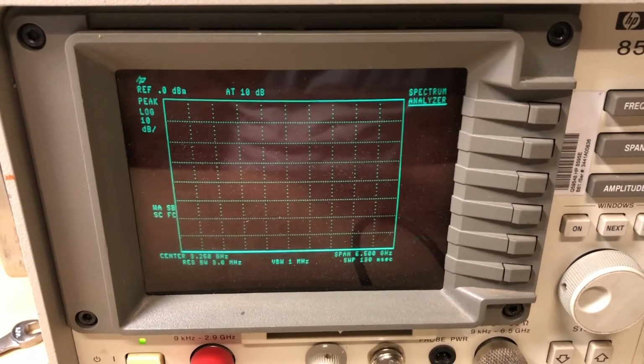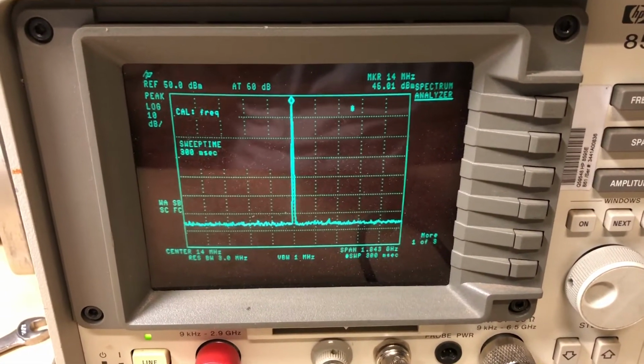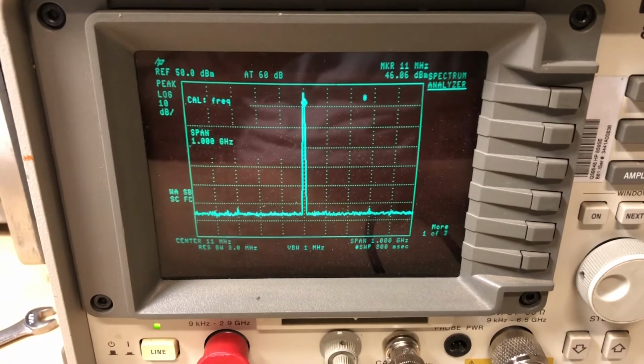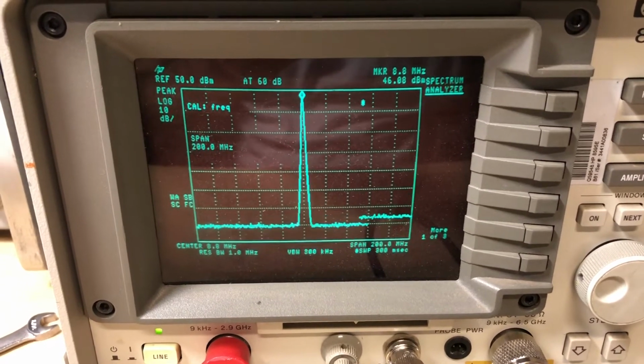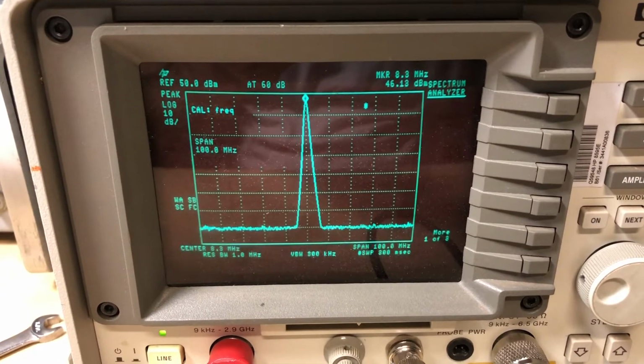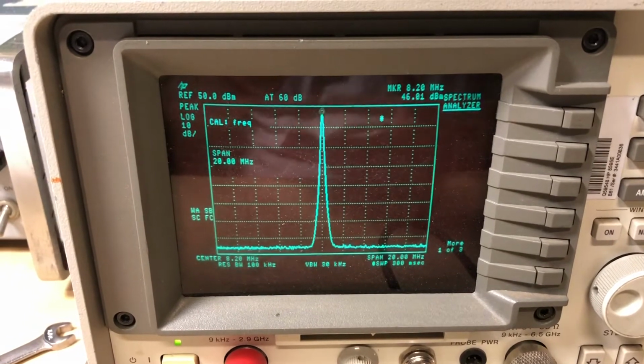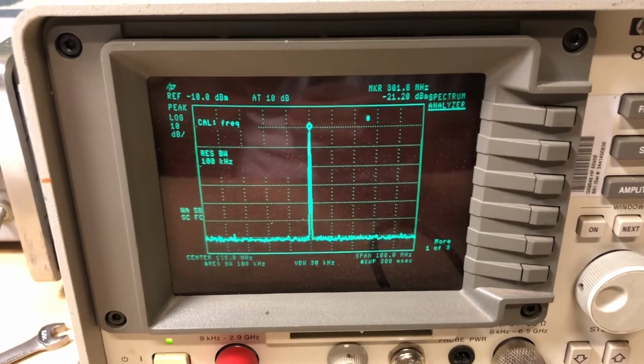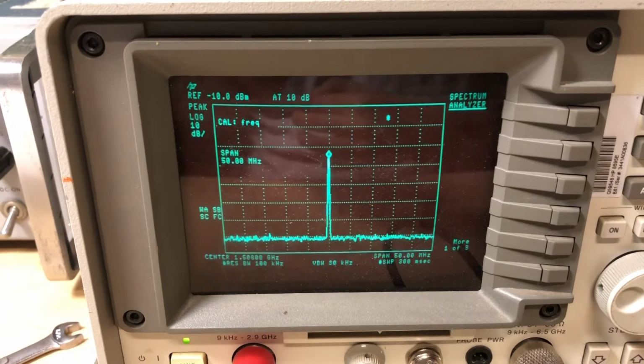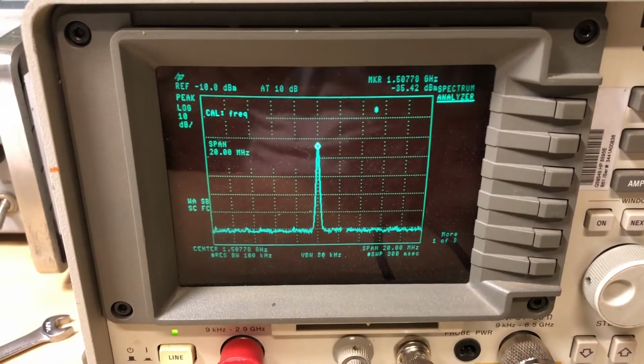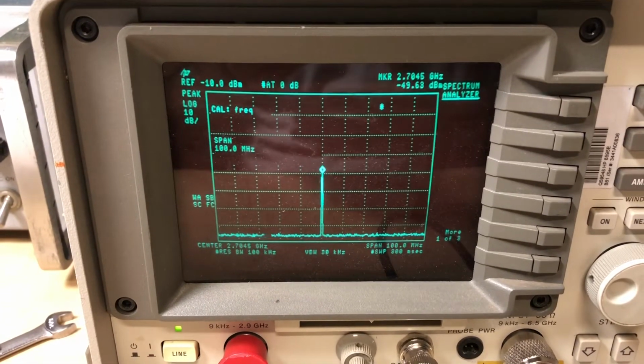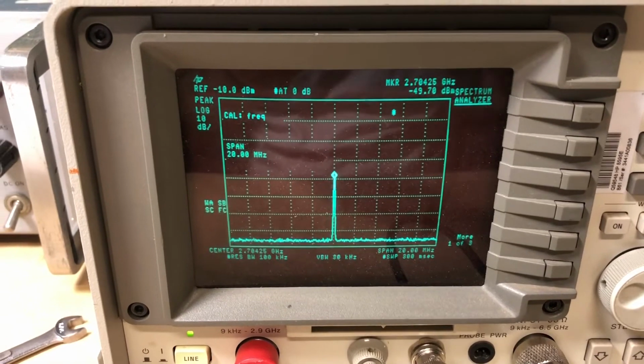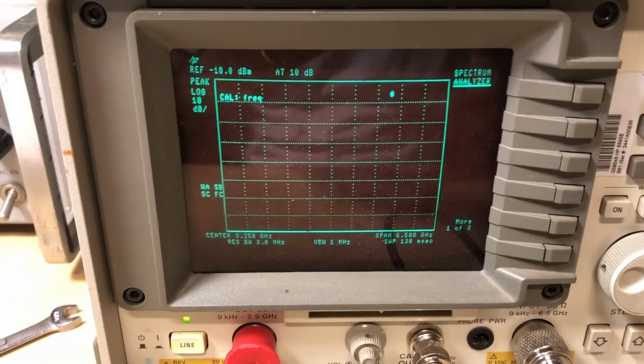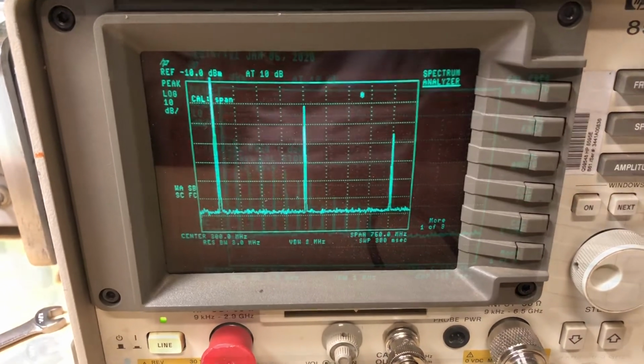All right, let's run the cal frequency routine now. The manual specifies that when you run the cal frequency and the cal amplitude, you should run the cal frequency routine first. It's written out that way in the manual. There are measurements and adjustments that the cal frequency routine makes that will affect the cal amplitude. That's why it specifies to run the cal frequency first.